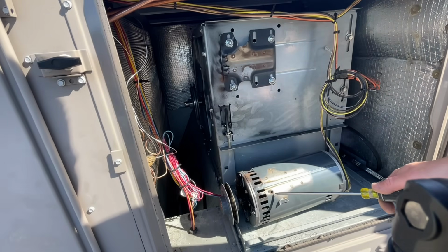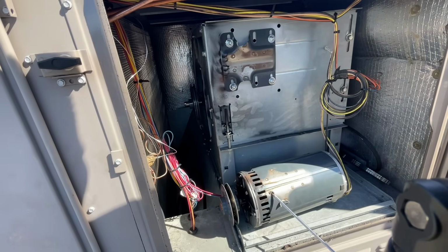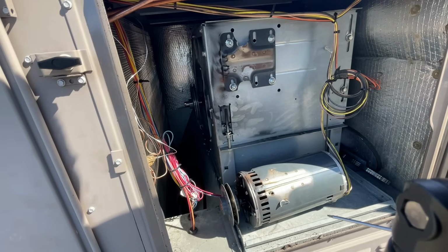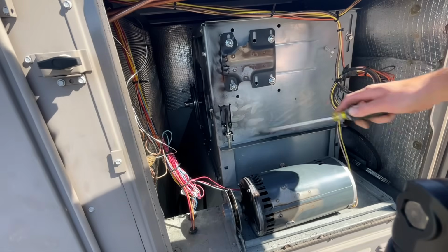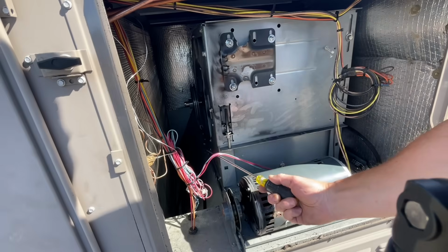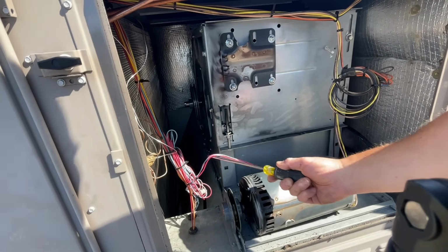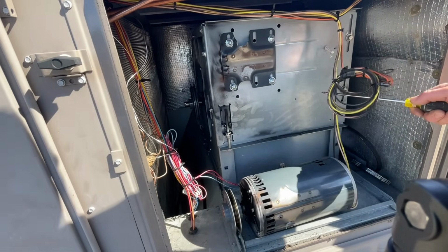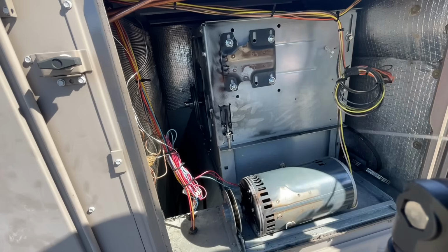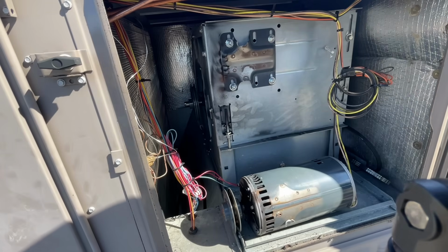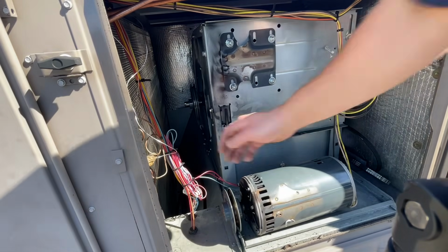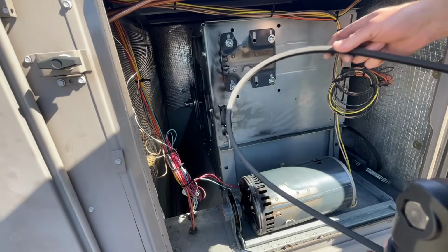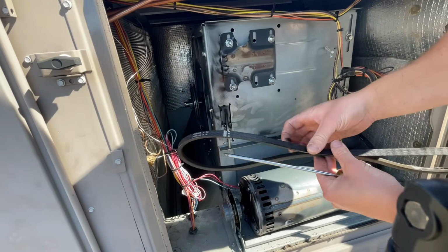These welds to fail and just rip right out. And the even funnier thing is, it didn't damage any of the wires. This is unbelievable. This motor dropped. It could have pinched all our high limit wires here. It could have torn this right out, which is our main power, blew our breaker downstairs, caused all kinds of issues, but it didn't. Here's our belt. I mean, our belt looks fairly new.